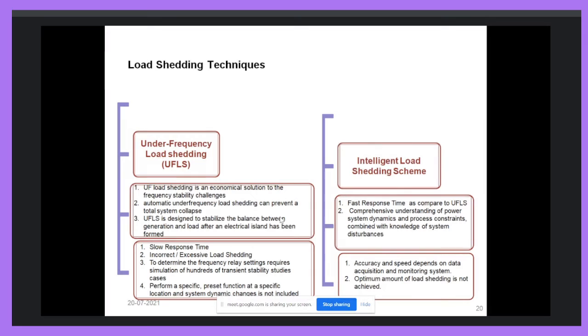Also collected some information about the under frequency load shedding and intelligent load shedding schemes. Compared these schemes, under frequency load shedding is an economic solution to the frequency stability challenge, because these types of schemes do not require much infrastructure. They are relay based load shedding schemes; we only have to use the relay for the load shedding.